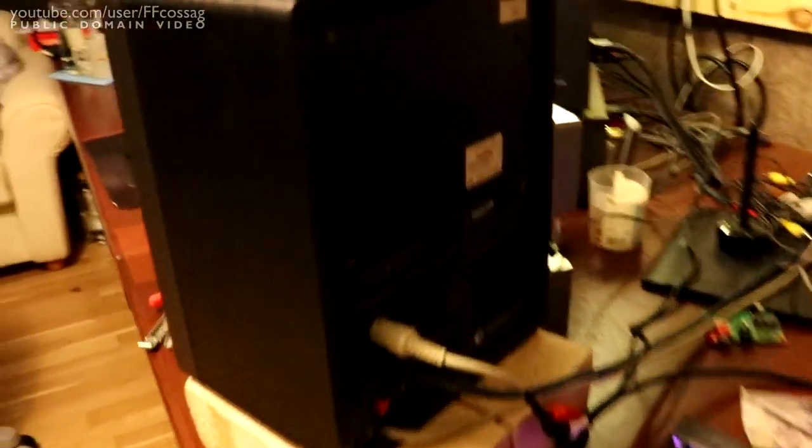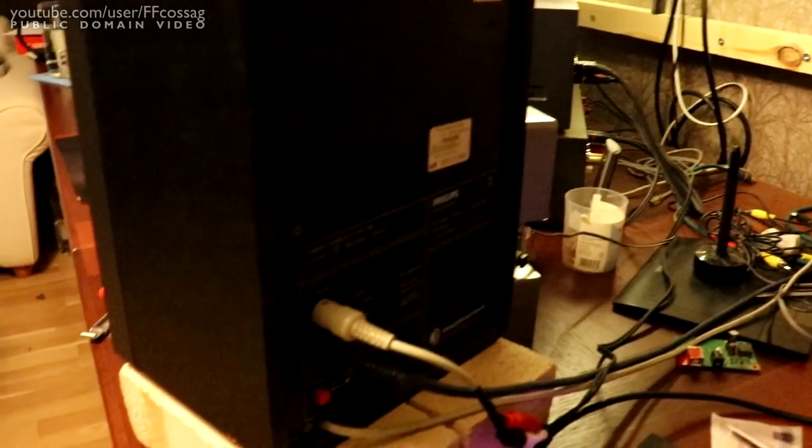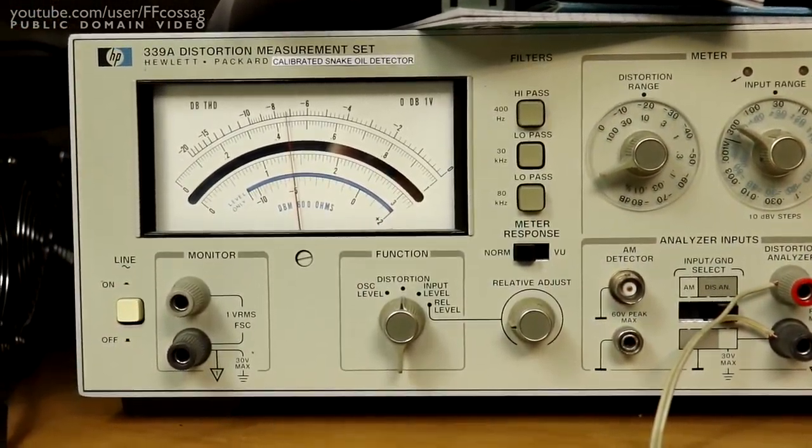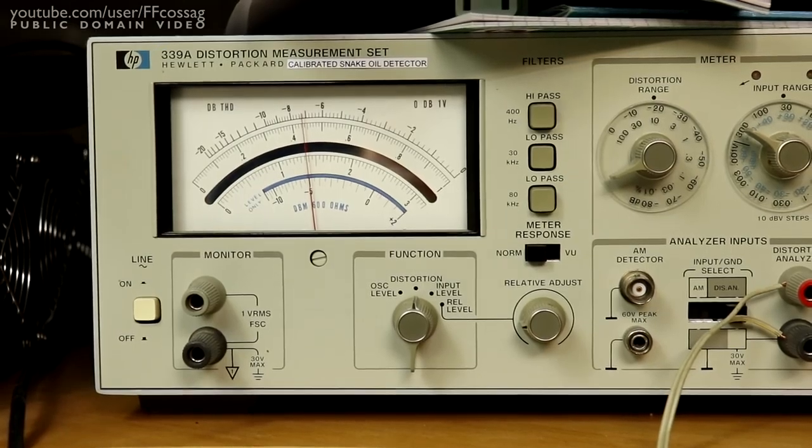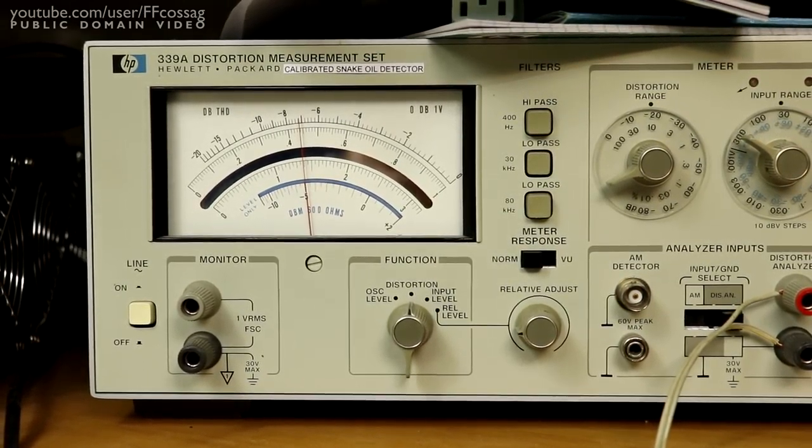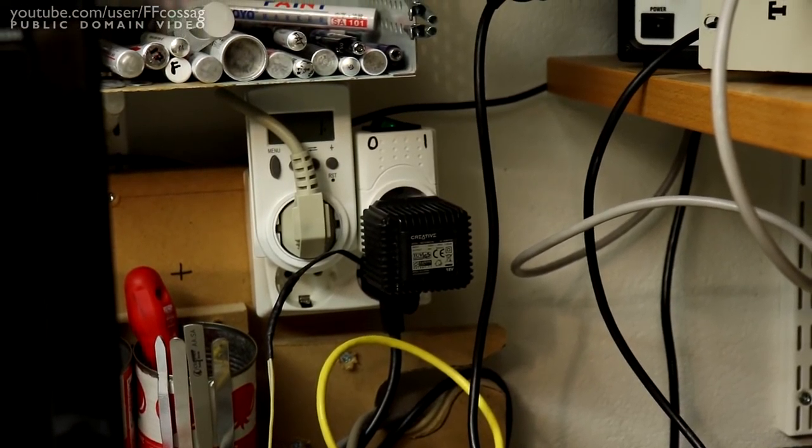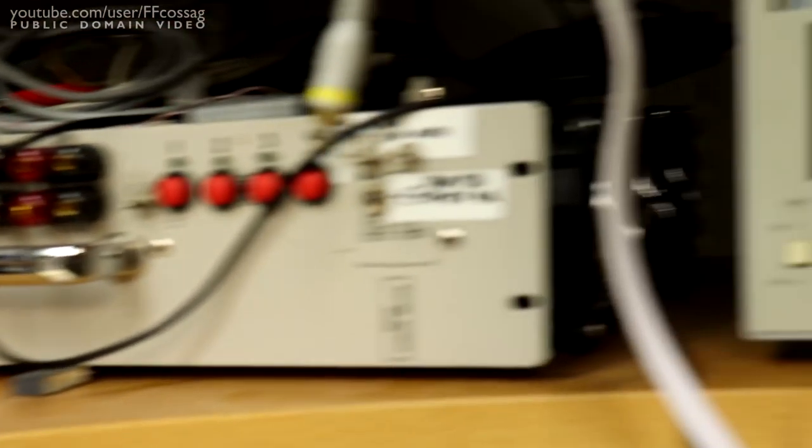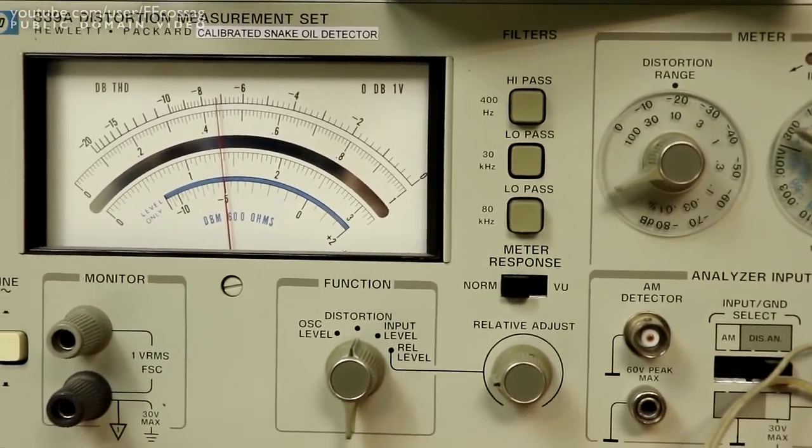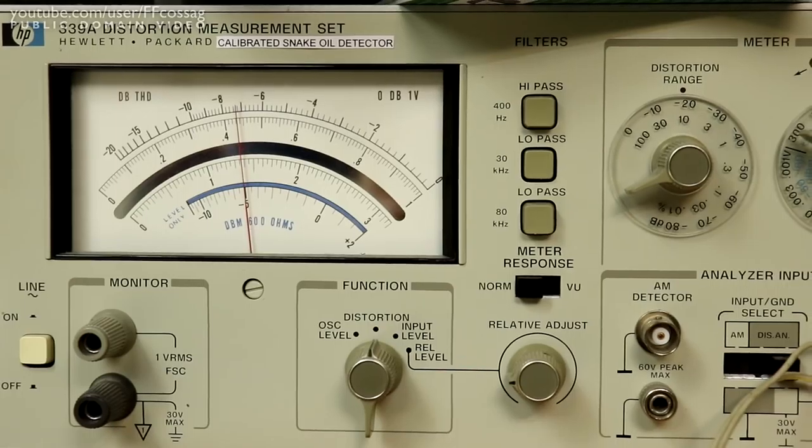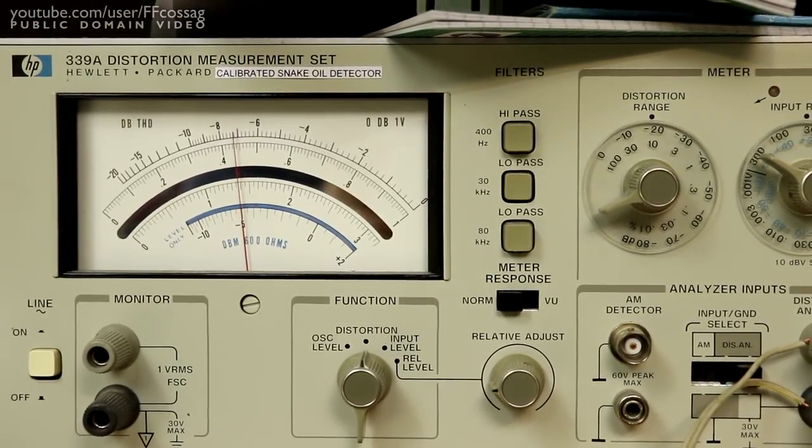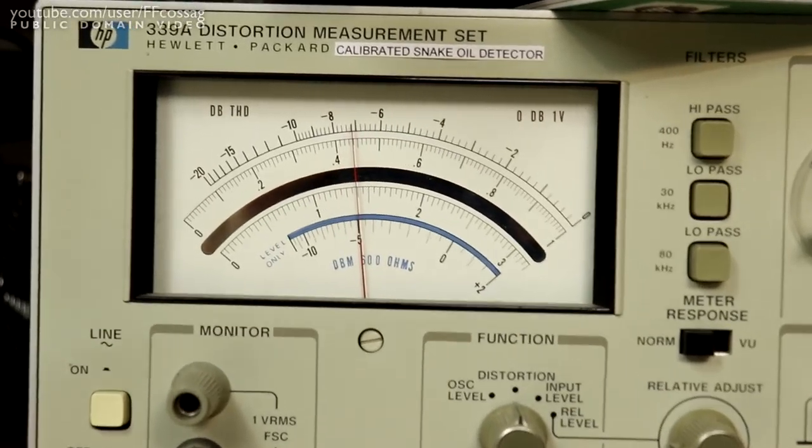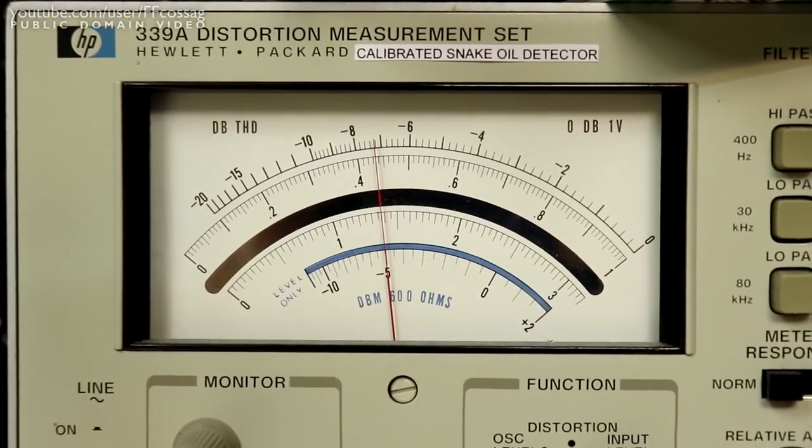Down in the workshop, we've hooked the distortion meter into the power grid. I've just got an AC transformer which is feeding straight into the meter. As you can see, we're in the 10% distortion range and we're seeing about 4.3%, 4.4% of total harmonic distortion and noise on the line right now.